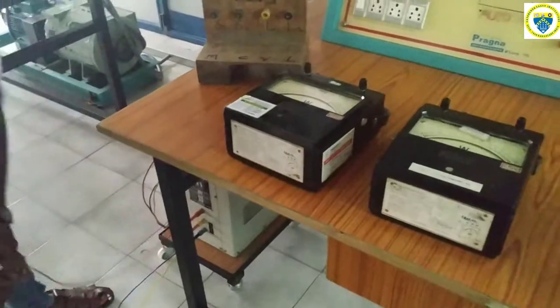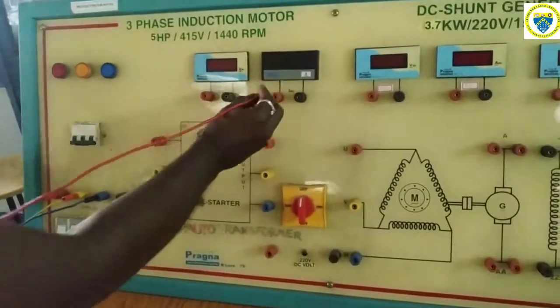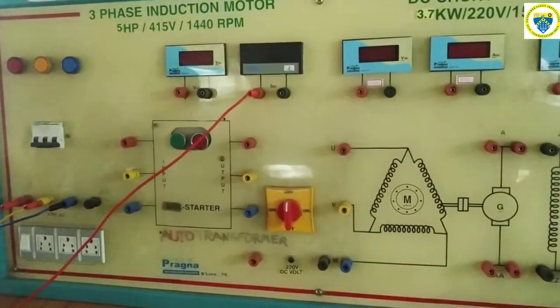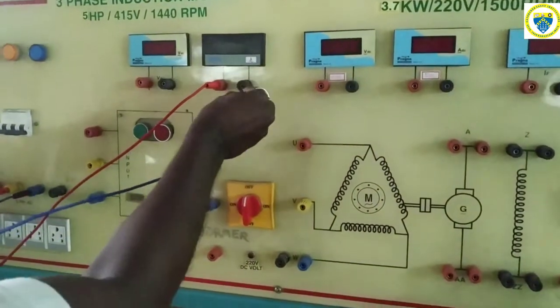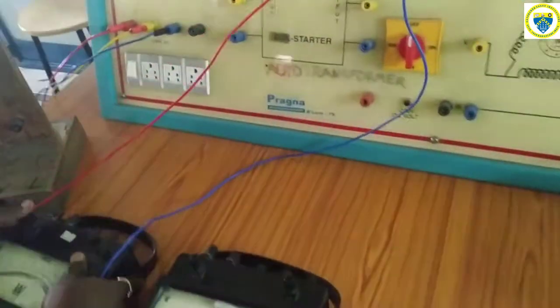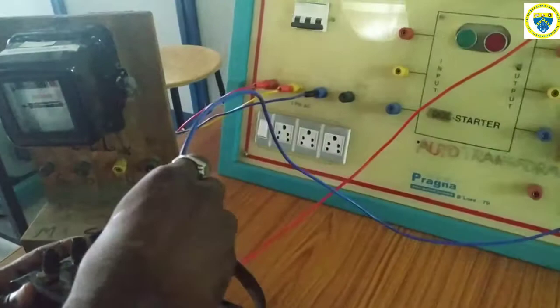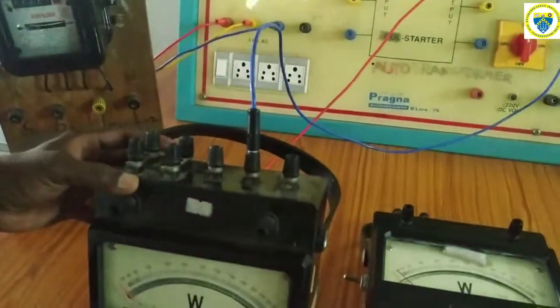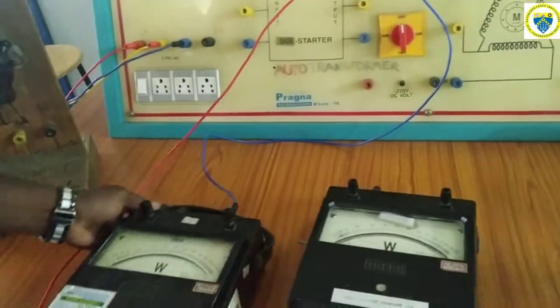From the R phase of the auto transformer, the R phase should go to the ammeter. Then the other terminal of the ammeter should go to the M terminal of wattmeter 1, the first wattmeter. Now MC should be shorted.